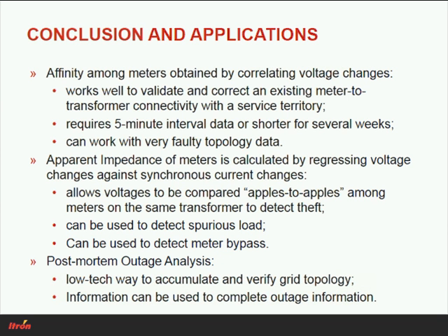The problem is that unless you're on a cellular network or on a fixed network, if you are on a mesh network, for example, that power out signal will often not reach the head end because it relies on other meters retransmitting. That's why power outage signals are often inconsistent, or in a way that you do not hear from all meters that are in power outage.